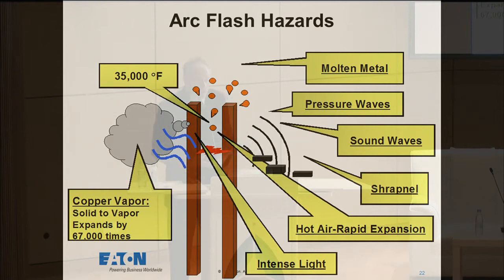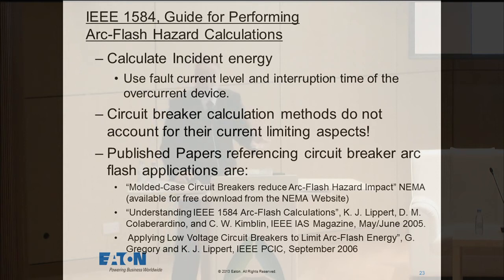What happens is you get high temperatures, 35,000 degrees Fahrenheit. The metal melts. The copper, when it vaporizes, expands by 67,000 times. And when that happens, this explosive force comes out. And it's interesting, when I talk with electricians, they say, I understood that when I touched it, it could stop my heart and kill me. I didn't understand about the arc flash hazard. So there's a lot of things going on, a lot of presentations, a lot of attention being paid to educate people about what arc flashes are and how we can prevent and mitigate them. So a lot of things happen here, and we have tools to help you prevent some of those occurrences.